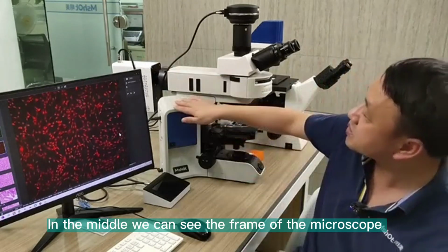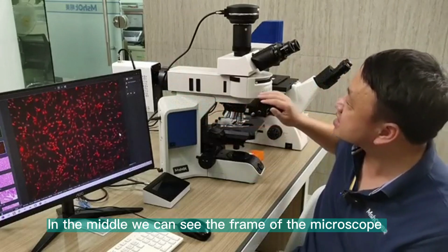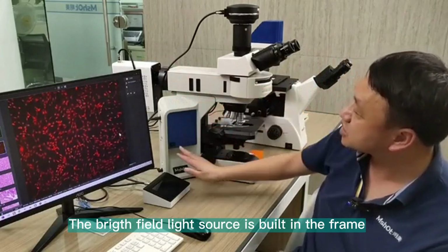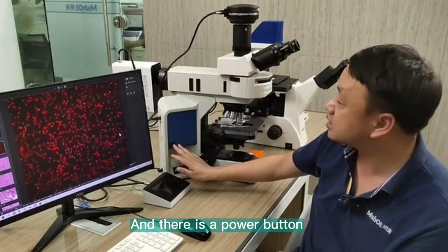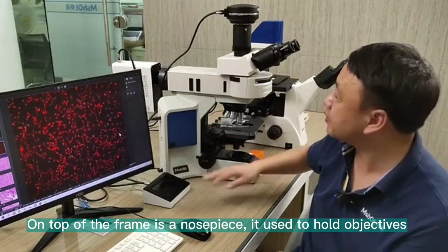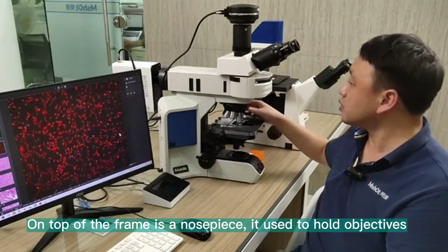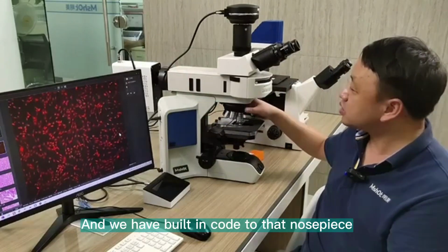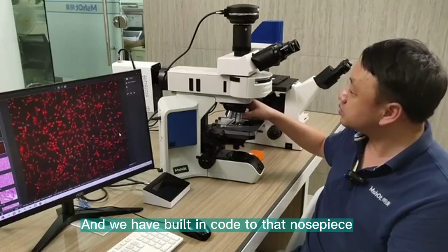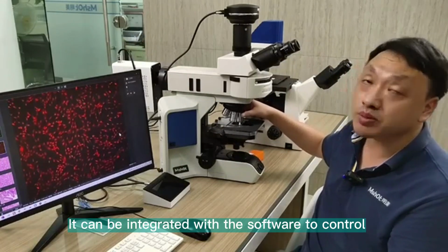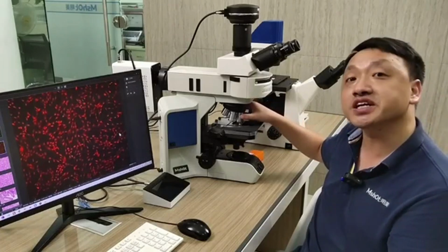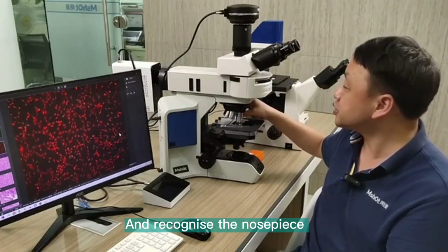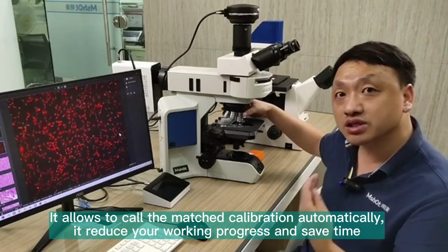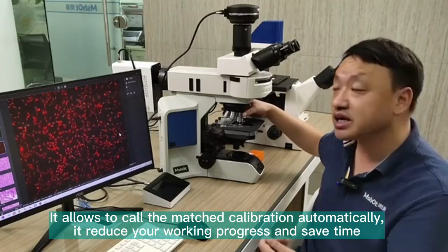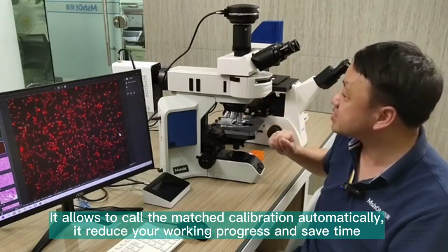In the middle we can see the frame of the microscope. The bright field light source is built into the frame, and there is a power button. On top of the frame is a nosepiece. It is used to hold objectives, and we have built-in code in that nosepiece. It can be integrated with the software to control and recognize the nosepiece. It allows the matched calibration to be called automatically. It reduces your working progress and saves time.